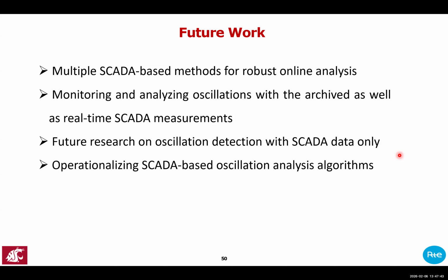And one of the weaknesses I should have mentioned is because it is based on SCADA with slow sampling or slow reporting, we cannot ascertain the frequency of oscillation. All we can say is there is an oscillation of this amplitude. Then we will still need PMU or DFR or some other faster signal to get information on the frequency itself. This method is all targeted towards the amplitude.